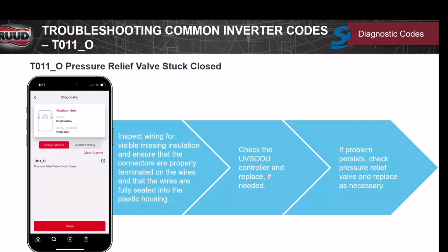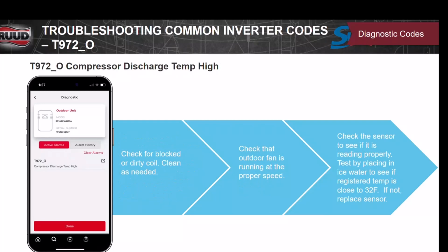So if we have a T011_O, this is the relief valve that we talked about. It's either stuck or it's not getting the proper control voltage. T972_O, discharge line high temperature. We want to check and make sure the coil's clean, number one, right? We want to look at the outdoor fan, make sure the fan's running at the proper speed, and you can do that through the app, right? See what its target is and where it's running. Then we check the sensor to see if it's properly reading by placing the sensor in ice water to make sure it lines up on the chart at 32 degrees.